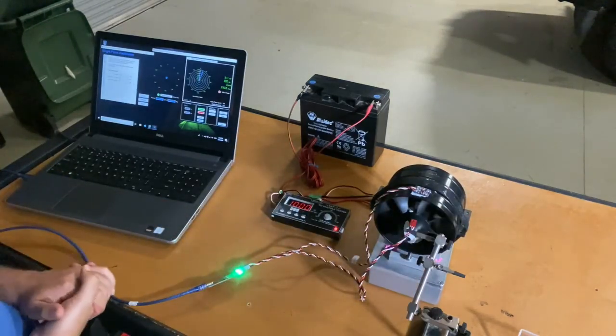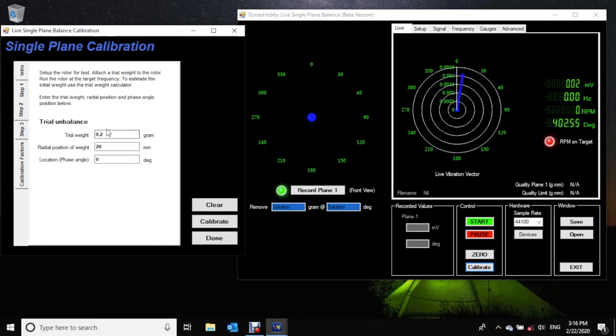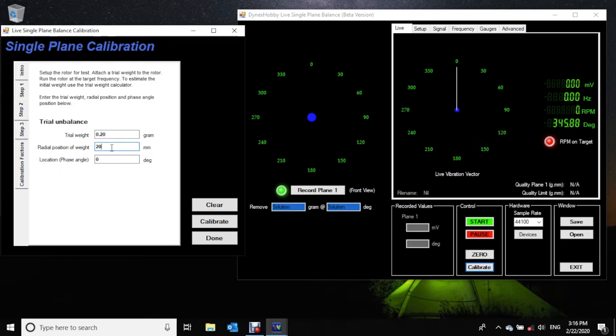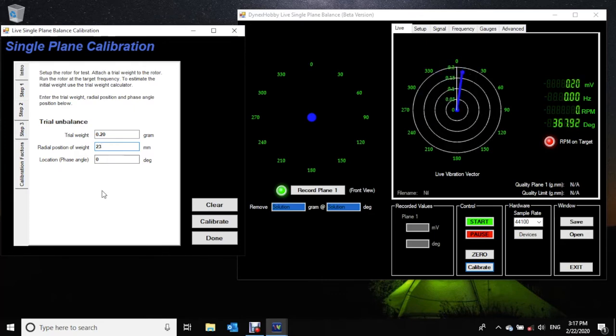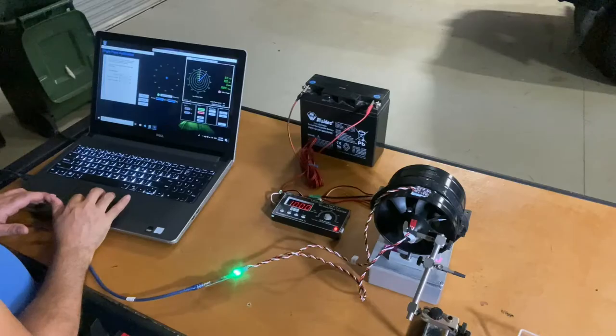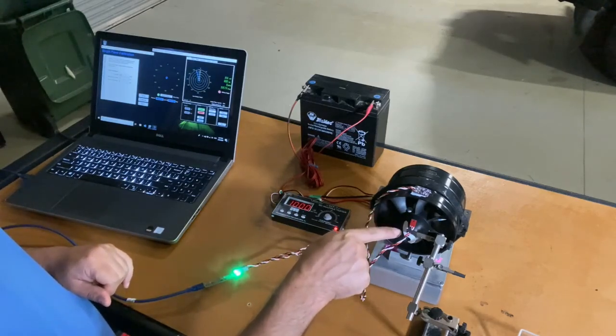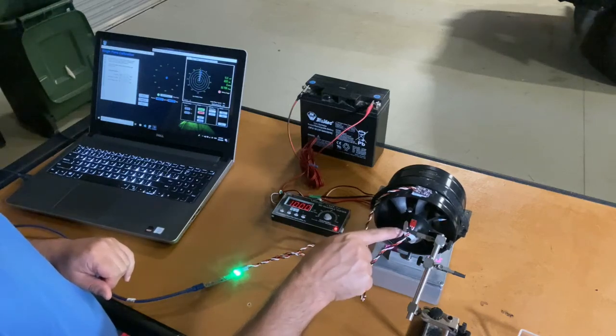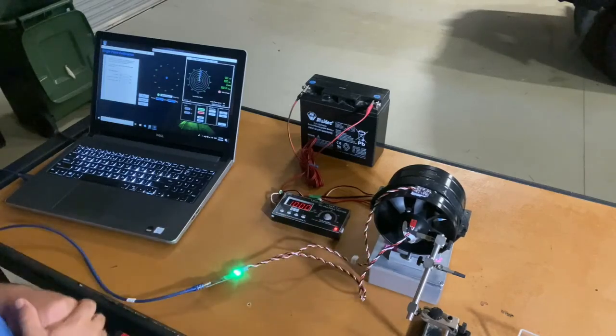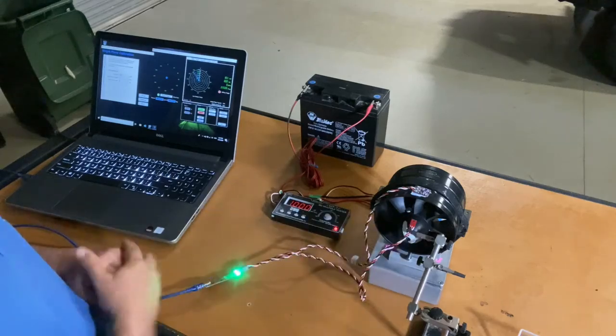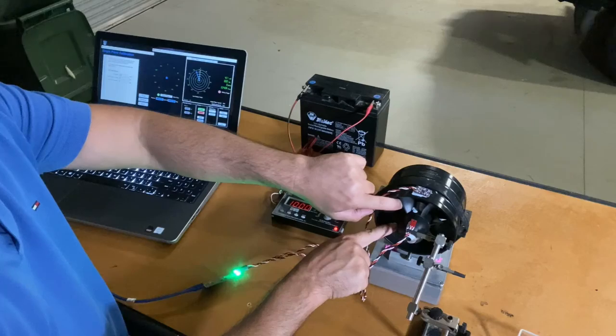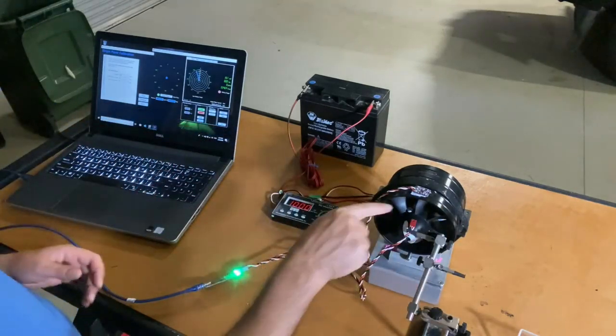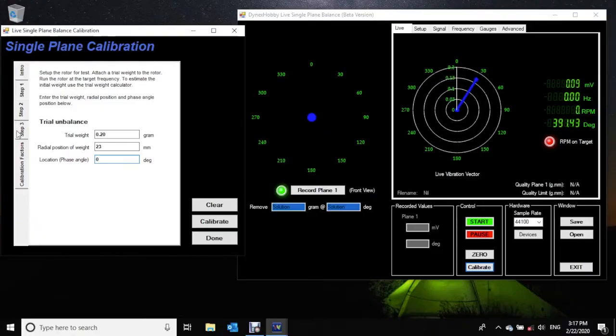Alrighty. So now I'm going to enter the weight into the calibration window. The trial weight is 0.2 grams. The radial position of the trial weight, as we measured previously, is 23 millimeters, so 23 millimeters from the center to where that trial weight is located. It's the radial direction that way. So I'll put 23 in the window. Once that is done, the phase angle or location of that trial weight is 0 degrees. In other words, that trial weight is located at an angle of 0 degrees relative to the white marker on the hub. If that trial weight is applied in any other position, say for example if it was applied here, it'll be 90 degrees, 180, 270, etc. But just to keep it simple, we tend to apply it at 0 degrees. So once that is done, we can move to step 3.